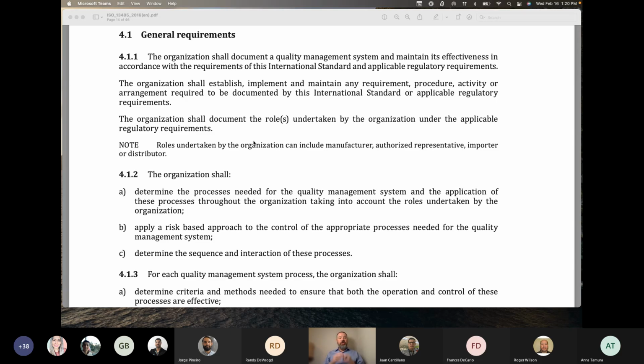So 4.1.1, you shall have a quality management system. You shall establish, implement, and maintain the requirements or procedures that are required by this standard. And you shall document the roles that you function within under the standard. So let's talk about 4.1.1. What does that mean? You have to have a quality management system. That quality management system should cover all of the requirements in this standard, specifically for the roles that your organization functions. So if your organization is a manufacturer only and you do not do any design controls, then you have to have a quality system. It has to cover everything in this standard, but it does not have to include design controls. Taking those 3 shalls in total helps begin to frame out what your quality management system is going to look like at the very highest level.